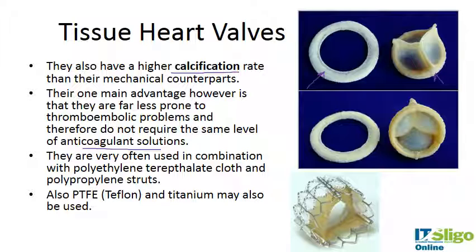Here is an example showing the cuff, which might be a titanium or polypropylene strut coated in PTFE or polyethylene terephthalate cloth. The valve itself is hand-sewn into the cuffs to make one complete unit — there really isn't any other way to do it, and there are experts who specialize in sewing heart valves. The new stented collapsible valve uses a titanium stent with a woven section to allow tissue ingrowth, with a biological heart valve inside. The stent is collapsed, inserted on a balloon through the femoral artery, and guided up into the heart to the valve replacement site.